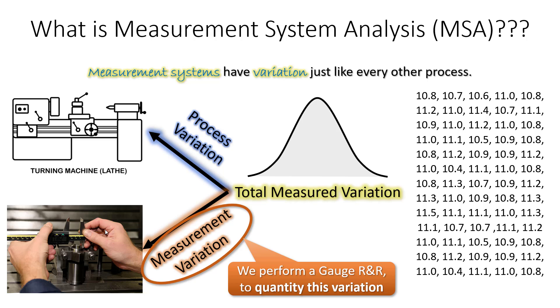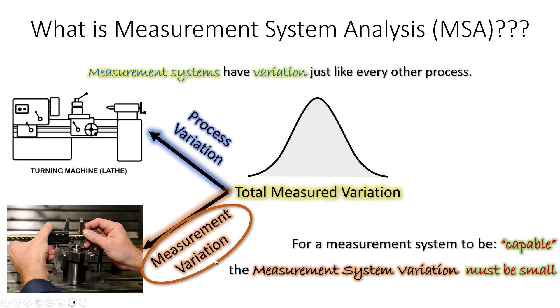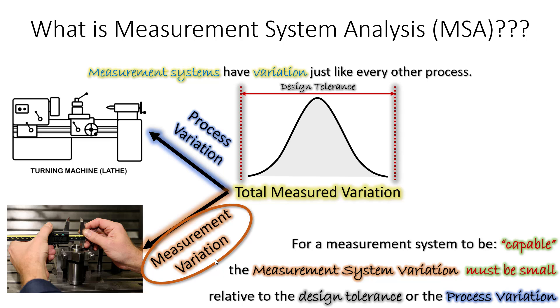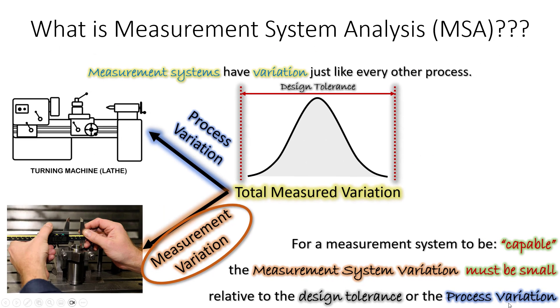That's why we do a gauge R&R — not just to quantify variation, but to evaluate whether we've chosen the right measurement system for the application. For a measurement system to be acceptable or capable for its intended purpose, the measurement system variation must be small relative to one of two things: either your design tolerance or your process variation. We'll talk about choosing between those two methods, when you'd use them, why, and how to do the calculations.